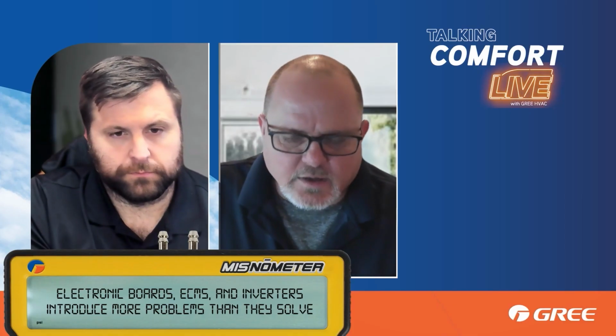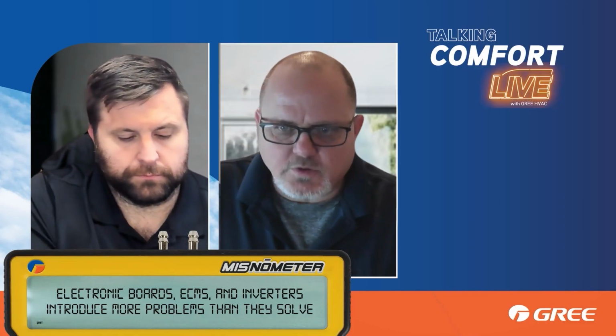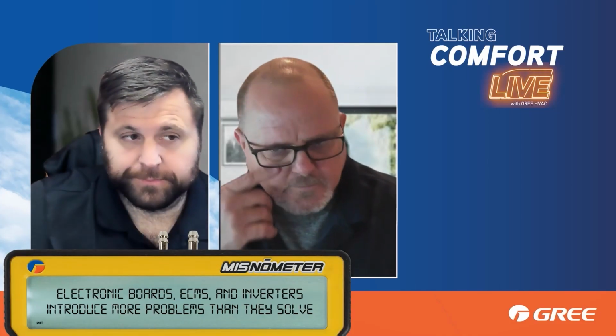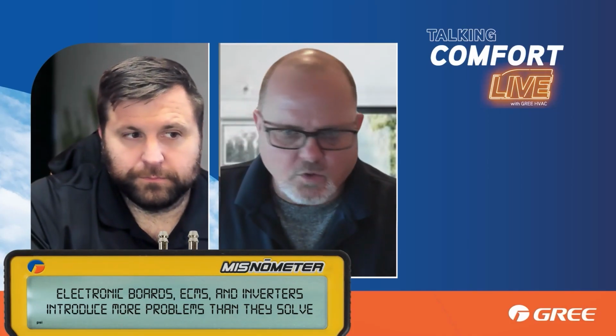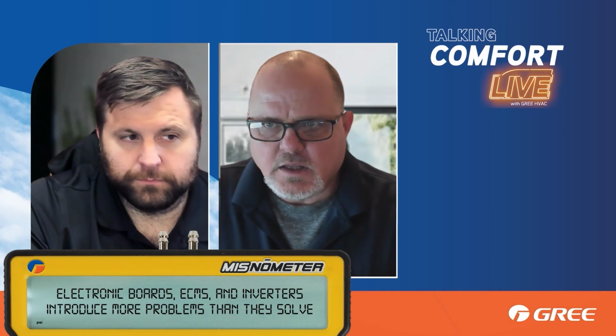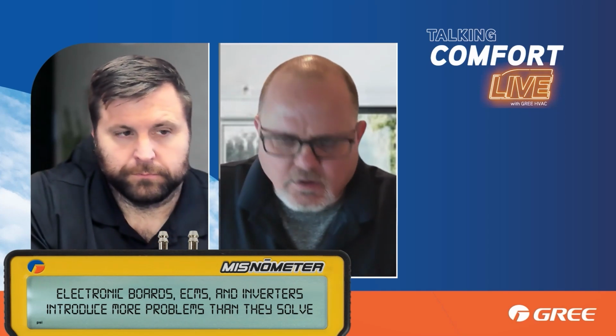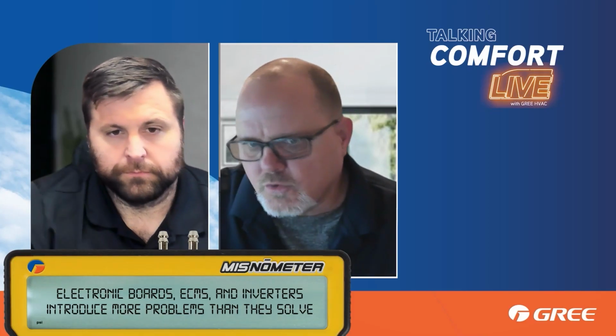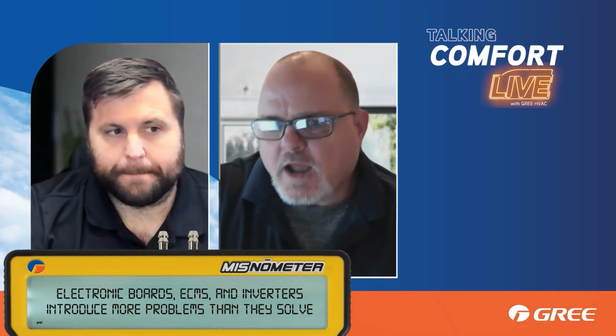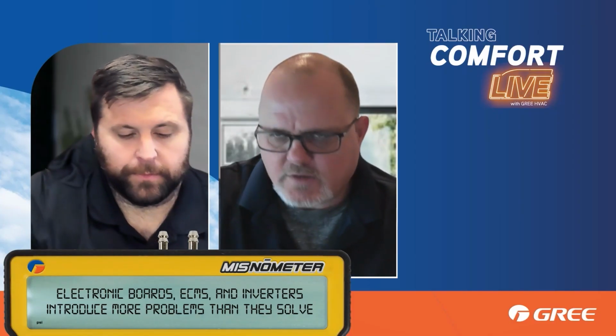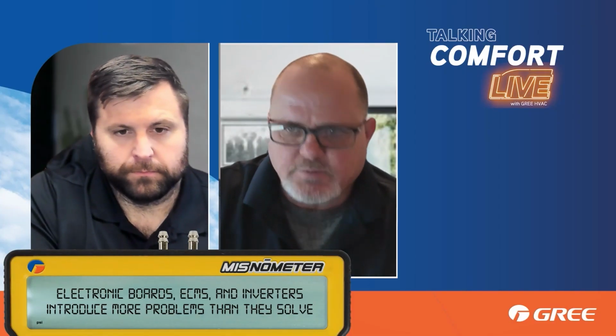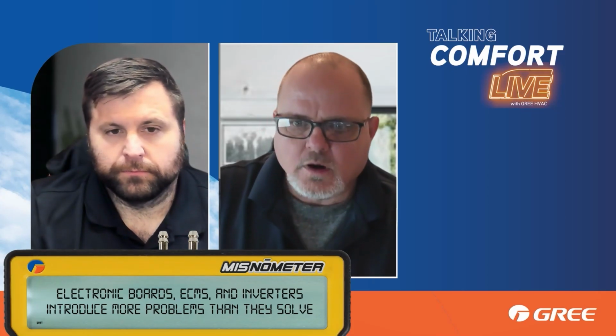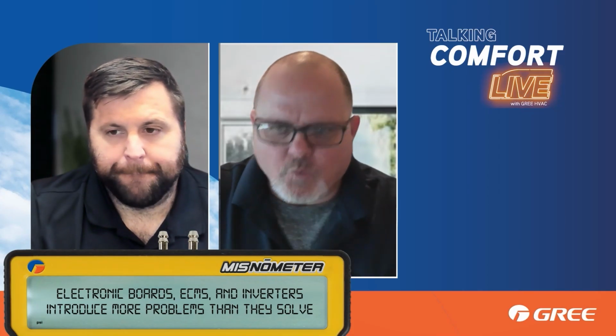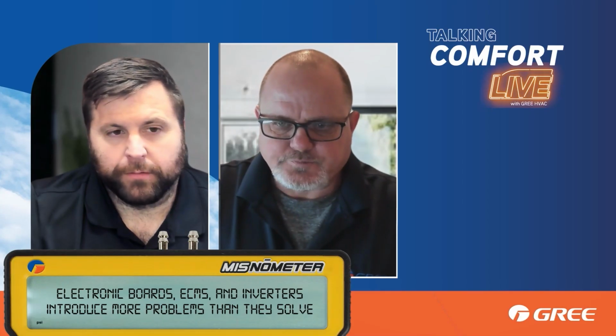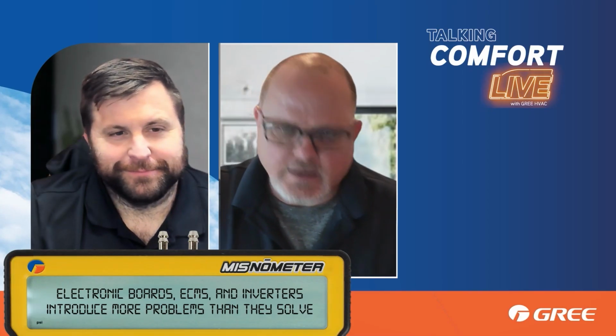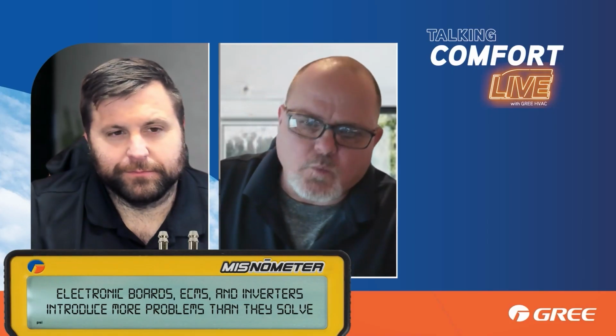So, I mean, I have an example I can give you. It was just recently, there was a multi-pro job that had 4 indoor units, and it wasn't heating very well. It was very cold inside the home. But the machine wasn't down. It wasn't out on an error code, but the end user knew the machine wasn't working properly. Inadvertently, what happened was, as they shut down some more of the heads, and never really shut them down, but just set the temperature to where that unit wasn't calling anymore, we quickly found that if we just left one indoor unit running, the machine stayed on and it worked. It heated. And it heated fairly well on that one head.